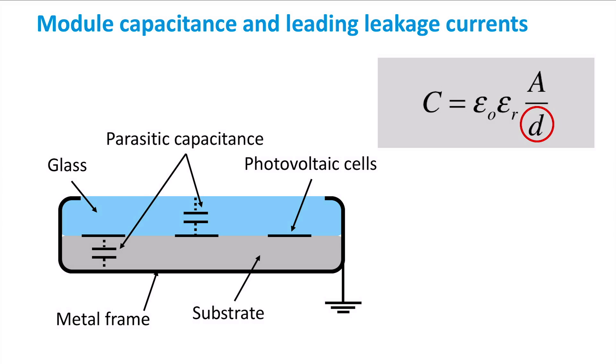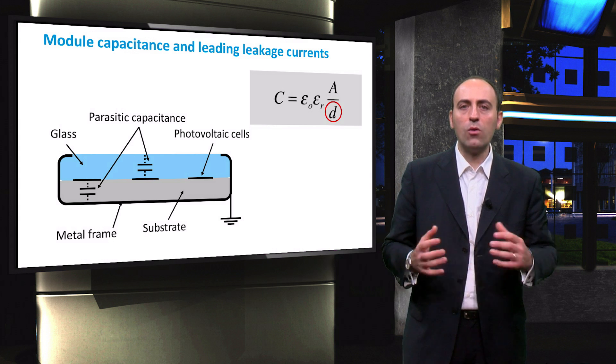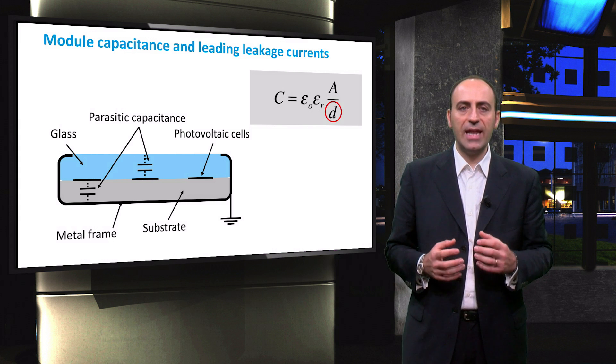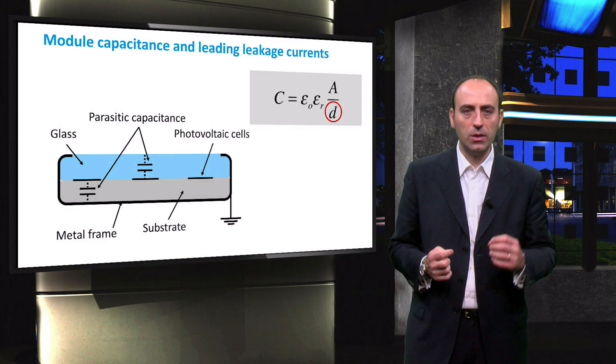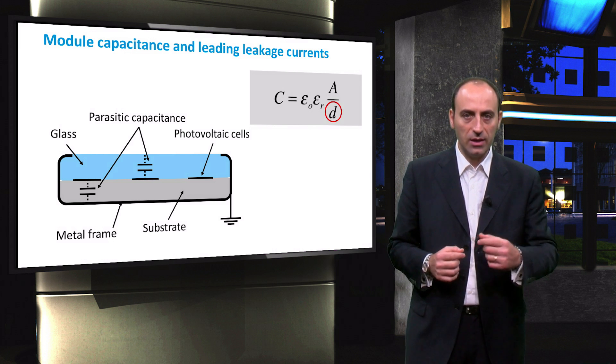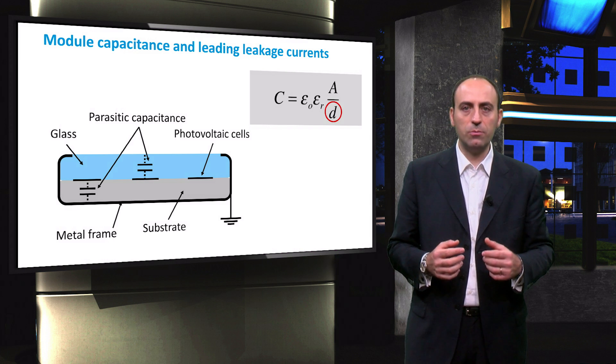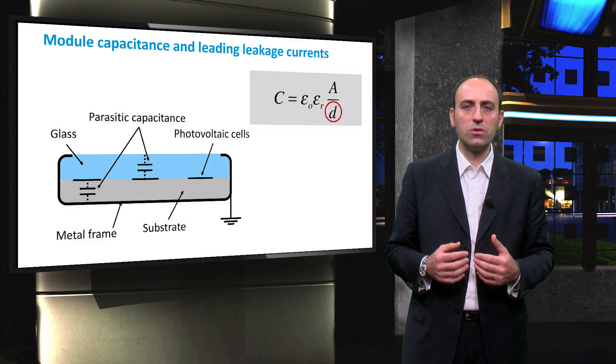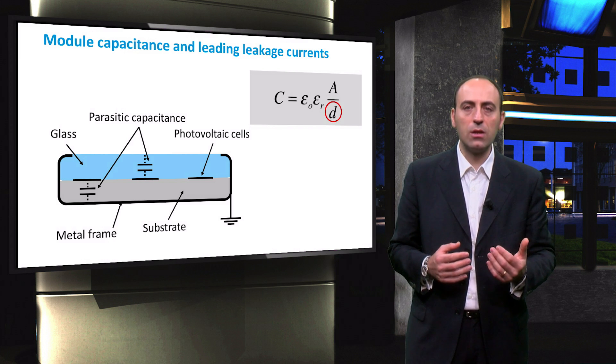and D is the distance between the two charged layers. As we saw when describing the overall configurations of the inverter, a transformer-less topology lacks the galvanic isolation between the PV array and the grid. In this way, the PV panels are directly connected to the grid, which means that there is a direct path for leakage ground currents caused by the fluctuations of the potential between the PV array and the grid.